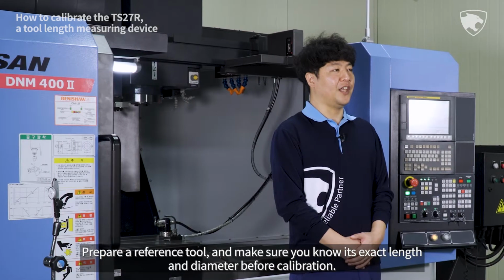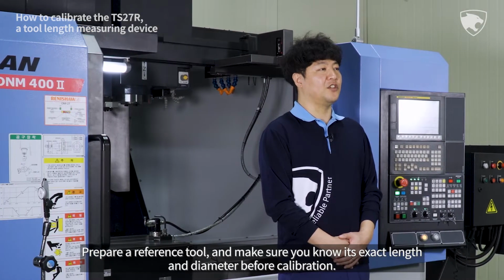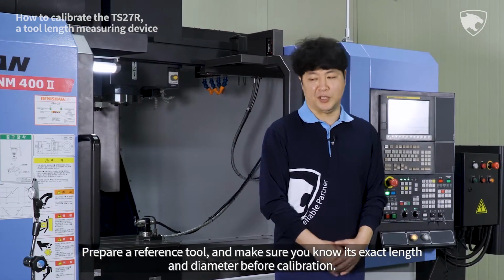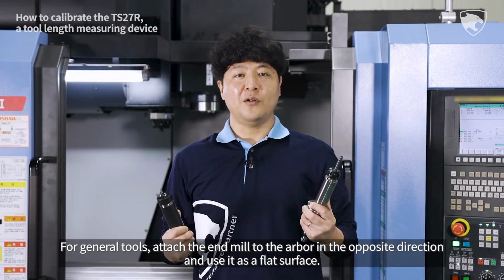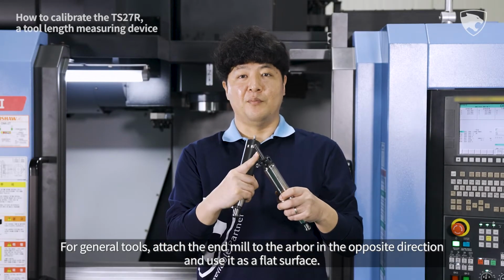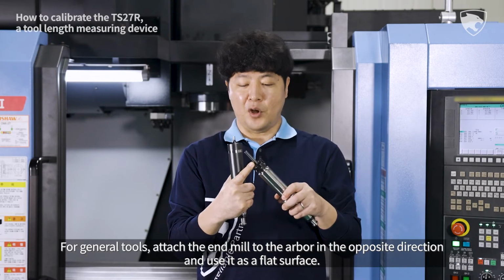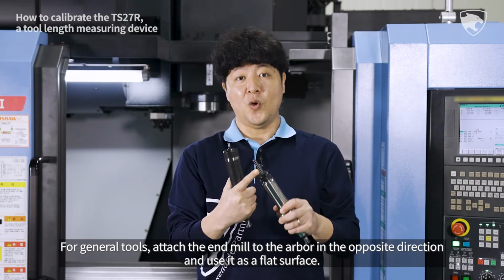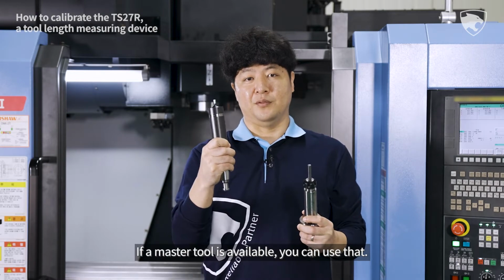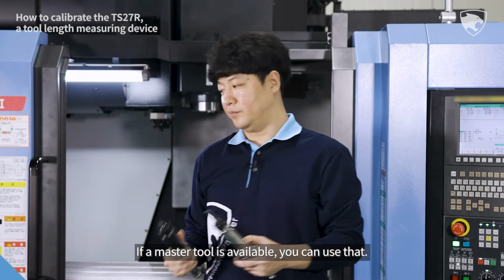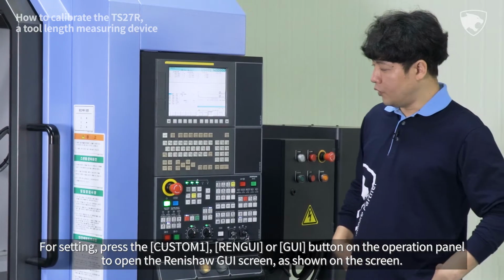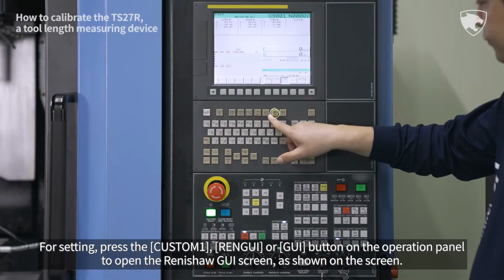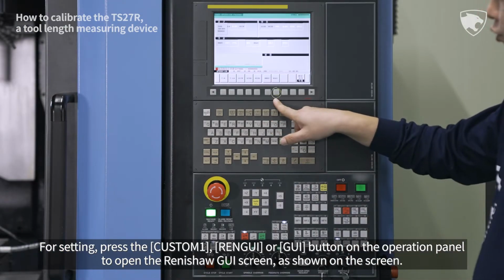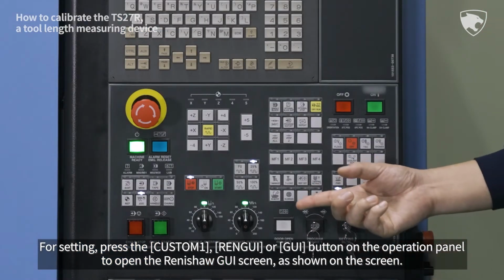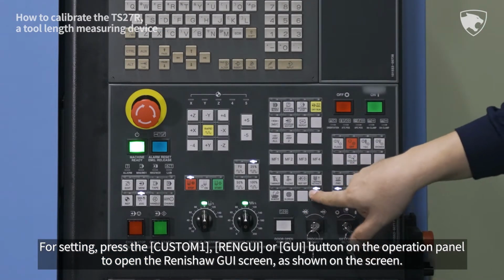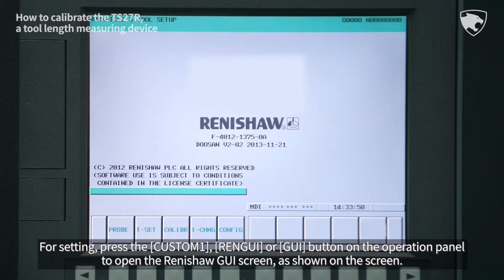Prepare a reference tool and make sure you know its exact length and diameter before calibration. For general tools, attach the end mill to the arbor in the opposite direction and use it as a flat surface. If a master tool is available, you can use that. For setting, press the Custom 1 REN-GUI or GUI button on the operation panel to open the Renishaw GUI screen as shown on the screen.